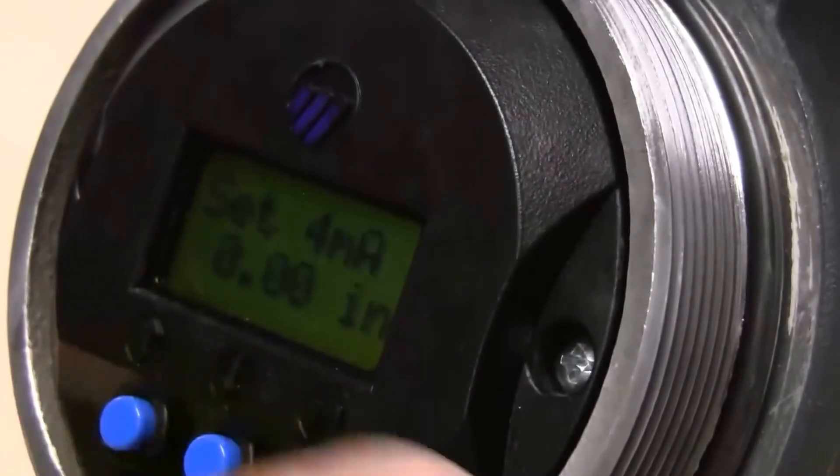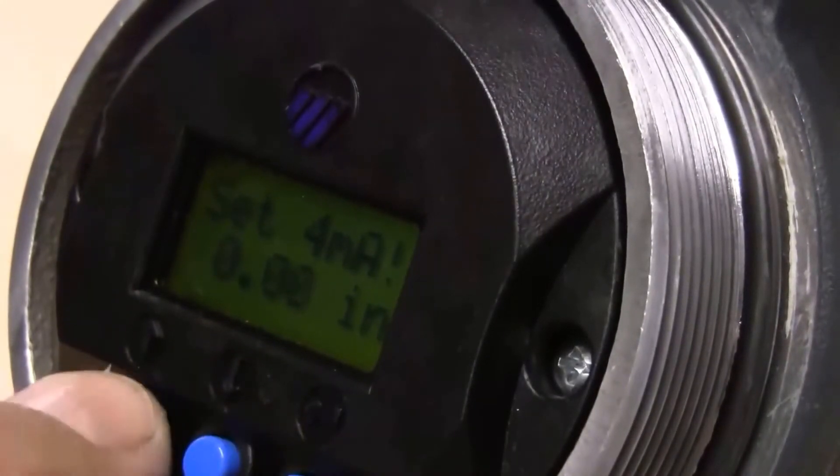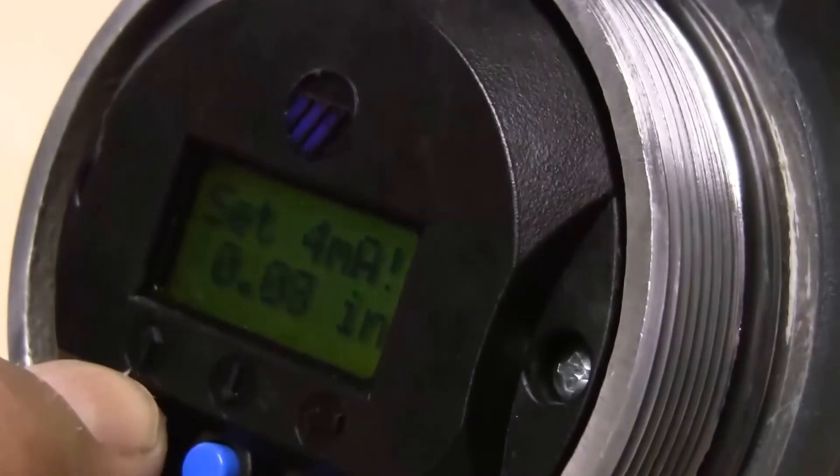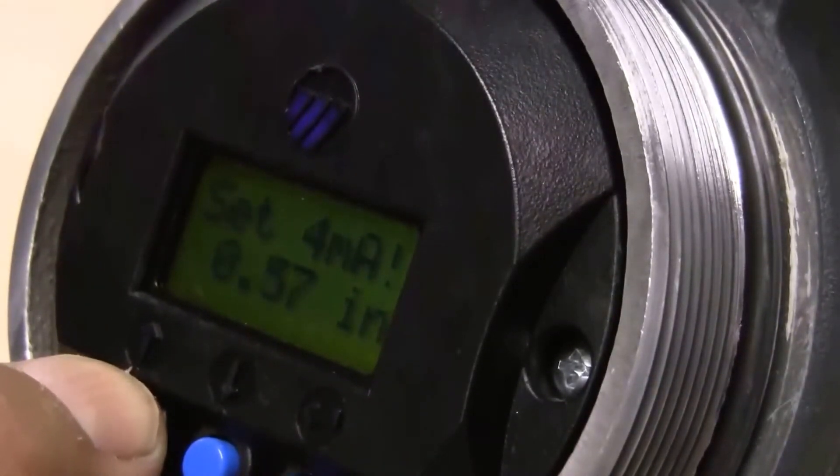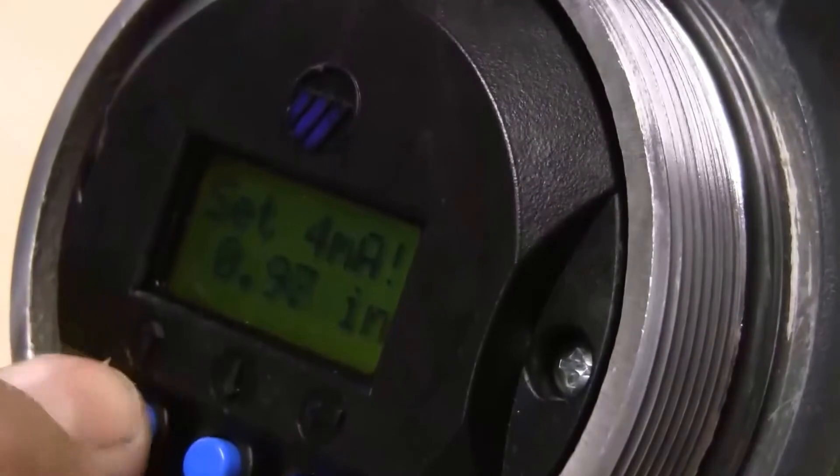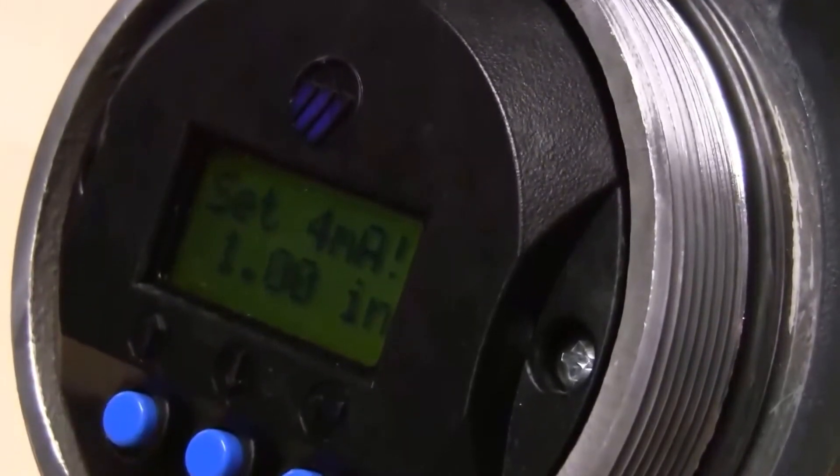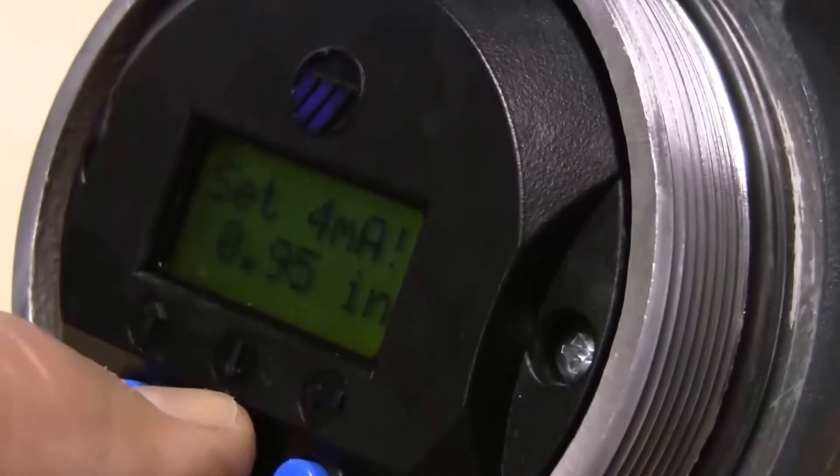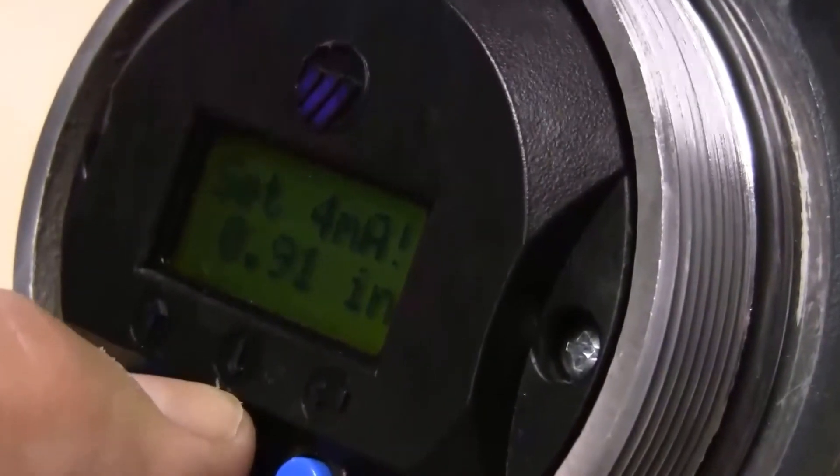And I want zero inches on the displacer to give me a four milliamp output. If I wanted it to be something else, I could simply enter and raise that up. If I wanted zero inches on the displacer, or if I wanted, let's say one inch on the displacer to give me four milliamps, I could change that and enter it in that way. We'll keep this at zero right now. So bottom of the displacer will give us four milliamps.